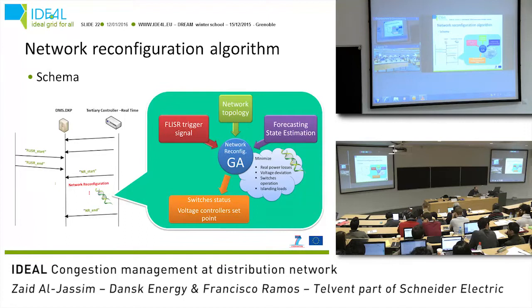It receives information like network topology, forecasting, and state estimation. And then it operates either on demand, which is, for example, by the FLISR system that can trigger the algorithm. And then the output will be the switch status and the voltage controller set point. Or the network configuration algorithm can also be used on schedule, like once a day, in order to optimize the operation of the network, or find the optimal configuration of the network.